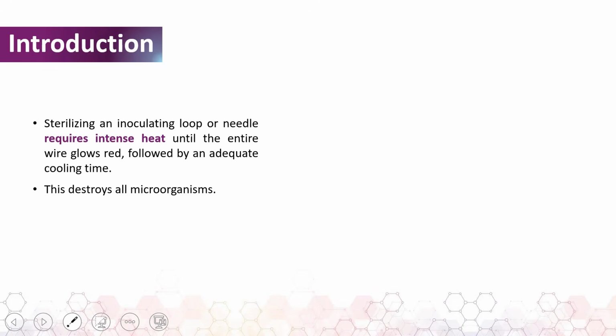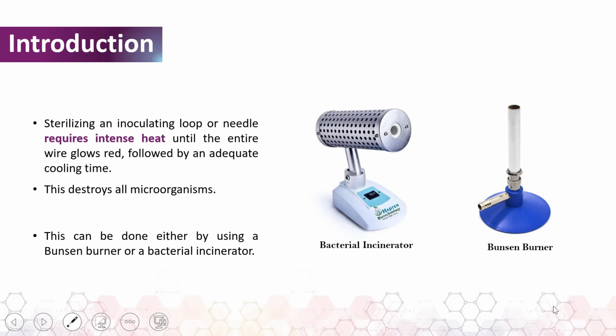The sterilization of inoculating loops or needles requires intense heat until the entire wire glows red, followed by an adequate cooling time, as these will destroy all microorganisms. And this can be done either by using a Bunsen burner or a bacteria incinerator. The bacteria incinerator sterilizes this equipment by exposing the metal wire to temperatures of about 800 degrees to 900 degrees Celsius for 5 to 10 seconds. The Bunsen burner also sterilizes this equipment by exposing the metal wire to a high temperature flame.